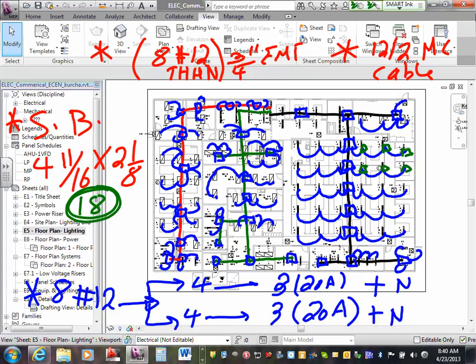You need to terminate it, Jeff, with something, right? You need to terminate up there. So please add, for these suspending ones, you don't need to use this type of box. Here's the smallest box, a smaller box like this. Actually, probably the shallowest 4x4 box that you can use with these, right at the top. So the stem can come into them, and you tie it to the branch circuit. So that's what I use, because these are direct, indirect lights. As you count, please go ahead and count these as boxes. Smallest box, 4x4 only.